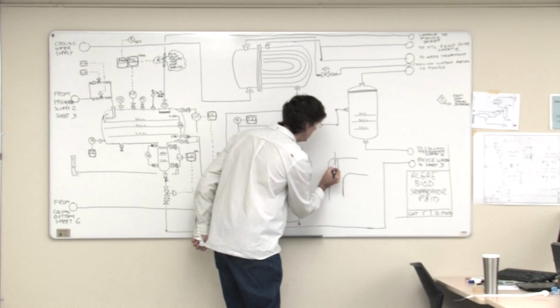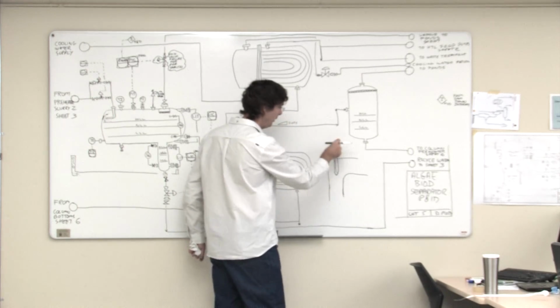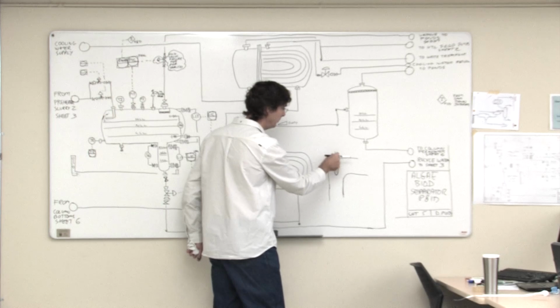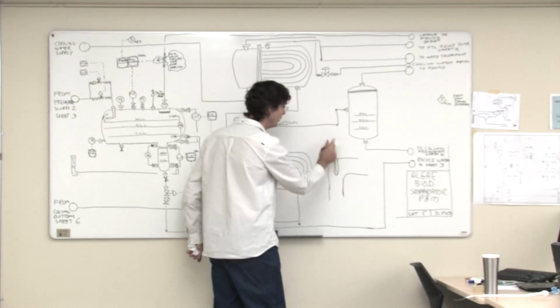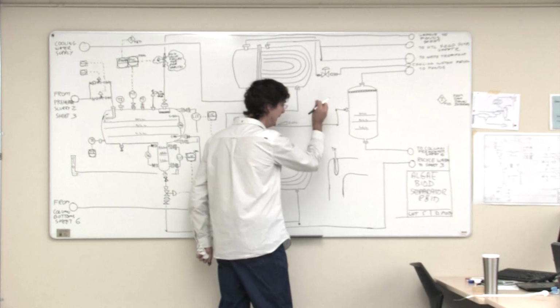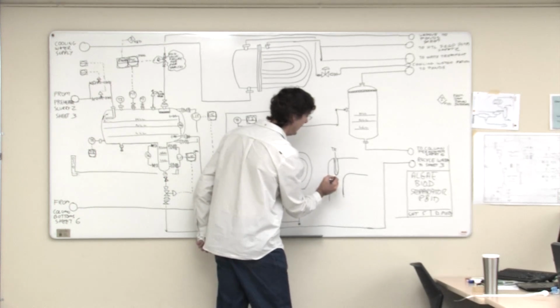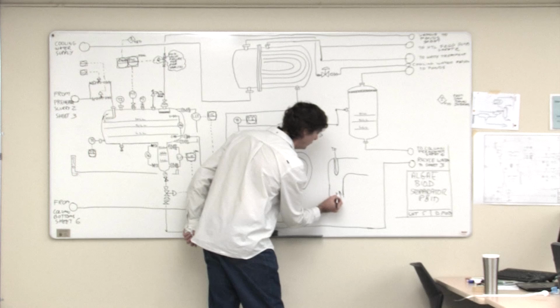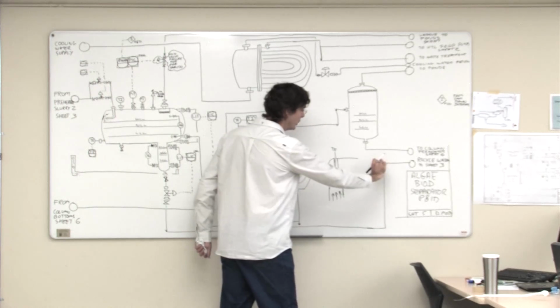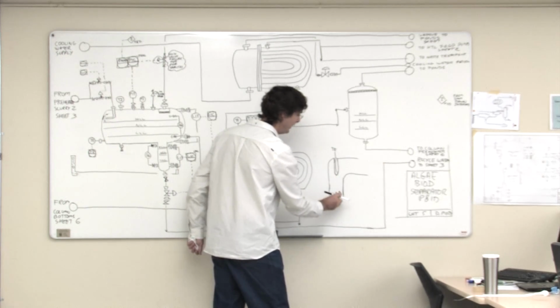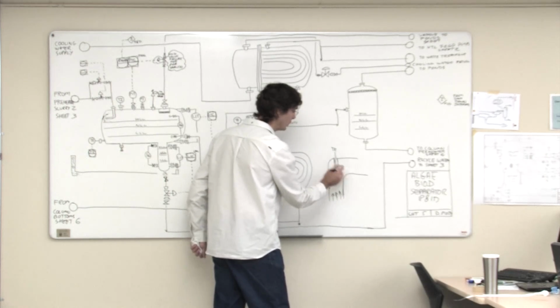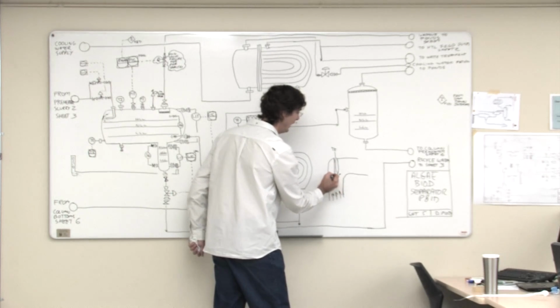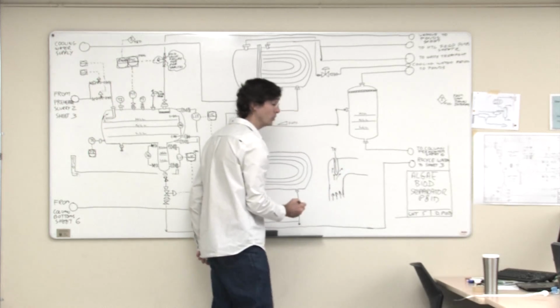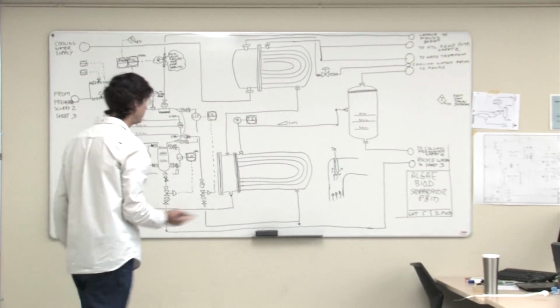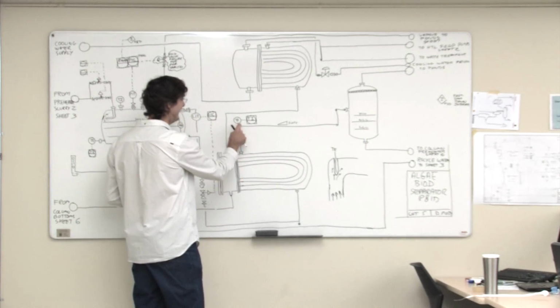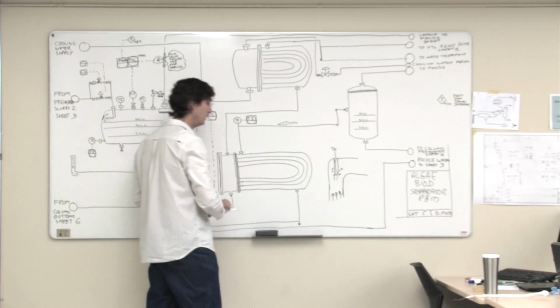Sorry, a thermowell. They drill a hole in the piece of steel and put in a pressure containing device, and then the TE, which is the RTD, can pop in and out of the thermowell. Whenever possible, they won't put it in a straight section of pipe. They'll put it right in an elbow where there's lots of velocity and turbulence, which improves heat transfer around the thermowell and gives faster response. That's why I showed the TE in an elbow, like that.